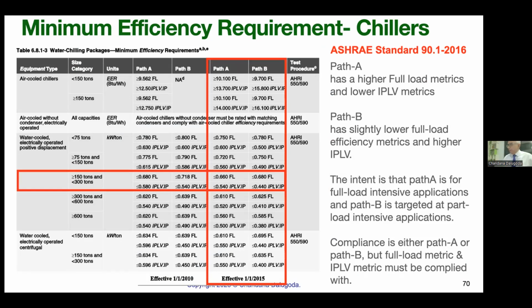ASHRAE 90.1 gives particular energy efficiencies. Now this is for water-cooled chillers, positive displacement type, like screw types, not centrifugal, screw types, scroll type chillers. Magnetic bearing chillers cannot be used here because those are centrifugal. So screw chillers, 75 tons, 75 to 150, 150 to 300, 300 to 600. So I have just 150 to 300. Your efficiency should be 0.66 kilowatt per ton at full load. Also, you'll have to check part load value, 0.540. We call it integrated part load value.